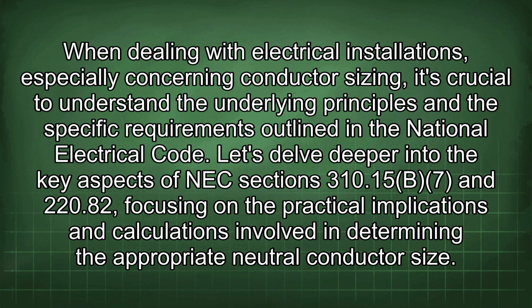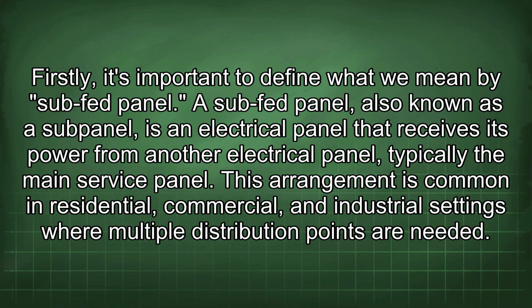Let's delve deeper into the key aspects of NEC sections 310.15(B)(7) and 220.82, focusing on the practical implications and calculations involved in determining the appropriate neutral conductor size. Firstly, it's important to define what we mean by subfed panel. A subfed panel, also known as a subpanel, is an electrical panel that receives its power from another electrical panel, typically the main service panel. This arrangement is common in residential, commercial, and industrial settings where multiple distribution points are needed.